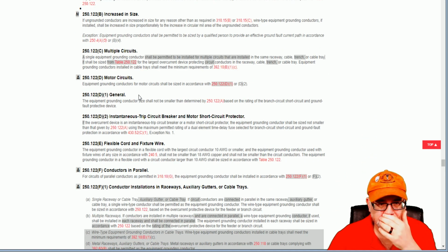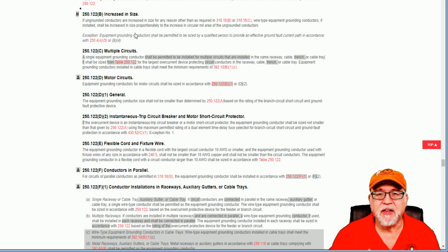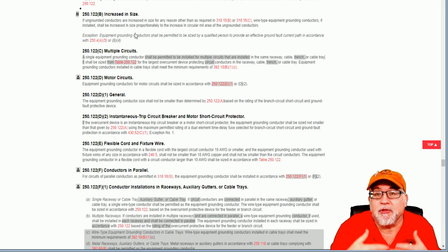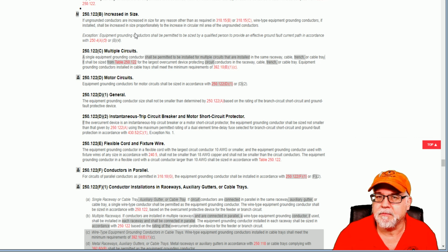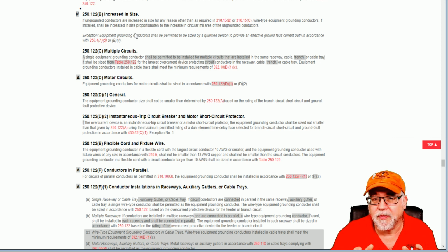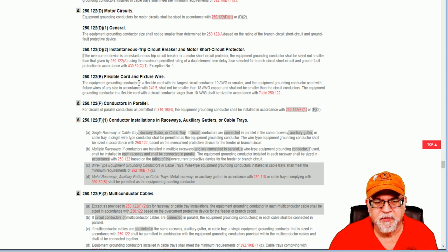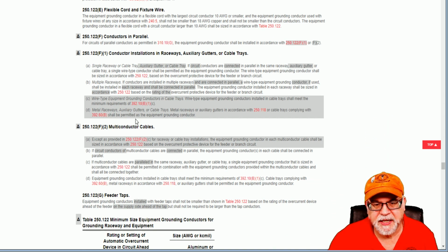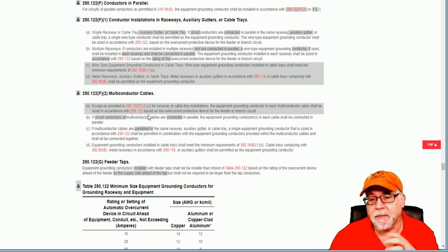A lot of information, like how to increase the size when you have things like voltage drop, or if an engineer requires you to increase the size of the ungrounded conductors for whatever reason. They don't have to have a reason, but if they increase them, then you have to increase proportionally the size of the equipment grounding conductor. We have a video on that as well. It's a simple formula. And of course, a bunch of information on paralleling applications, multi-conductor cables run in parallel and things like that.